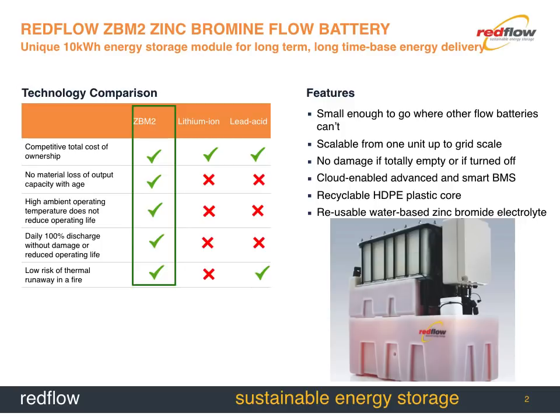Flow batteries also have something quite important for those of us who enjoy asset protection: they don't suffer from the risk of thermal runaway. Lithium batteries, one of the consequences of their high energy storage capacity, is a capacity to go into thermal runaway. If you put them in a fire they go bang, but also if they're in an energy system that shorts out, they can deliver that enormous amount of peak energy into a fault somewhere else in the system, which can actually result in a fire in and of itself.